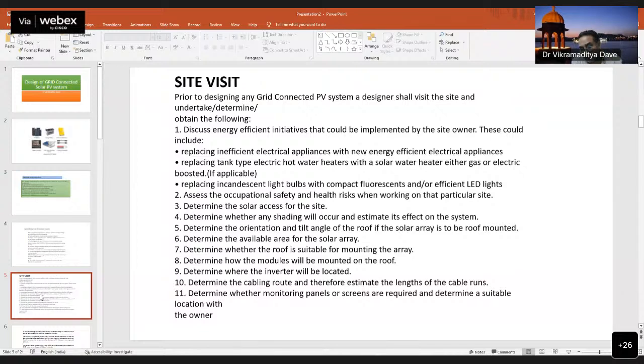फिर इन्वर्टर लोकेशन, कल ही मैं डिस्कस कर रहा था रात को कि है ना, इन्वर्टर भी ऐसी जगह लगाएं जो वो बरसात में खराब ना हो, पैनल के नीचे ना हो. अभी हमारे एक डिपार्टमेंट में पैनल के नीचे लगा दिया, तो जैसे एक सर्ज आई, ठीक है, उस सर्ज ने आग जैसे ही उगली, तो पैनल के नीचे लगा हुआ था, तो उसने केबल भी जला दी और पैनल को भी जला दिया. ठीक है, तो inverter should be in some room which may be at the bottom of the rooftop or may be located on the rooftop only.